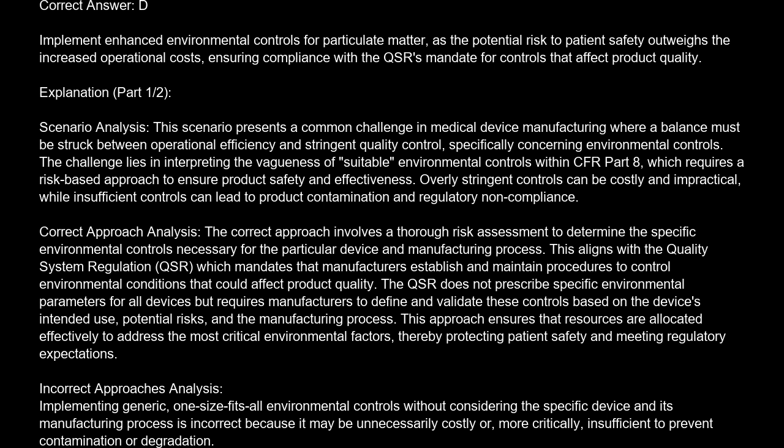The QSR does not prescribe specific environmental parameters for all devices, but requires manufacturers to define and validate these controls based on the device's intended use, potential risks, and the manufacturing process. This approach ensures that resources are allocated effectively to address the most critical environmental factors, thereby protecting patient safety and meeting regulatory expectations. Incorrect approaches analysis.